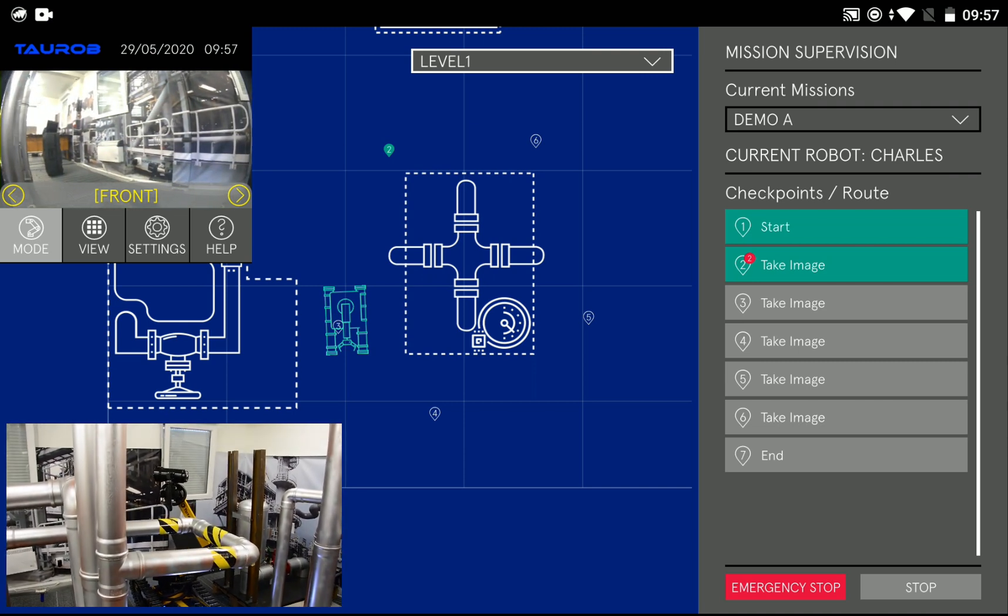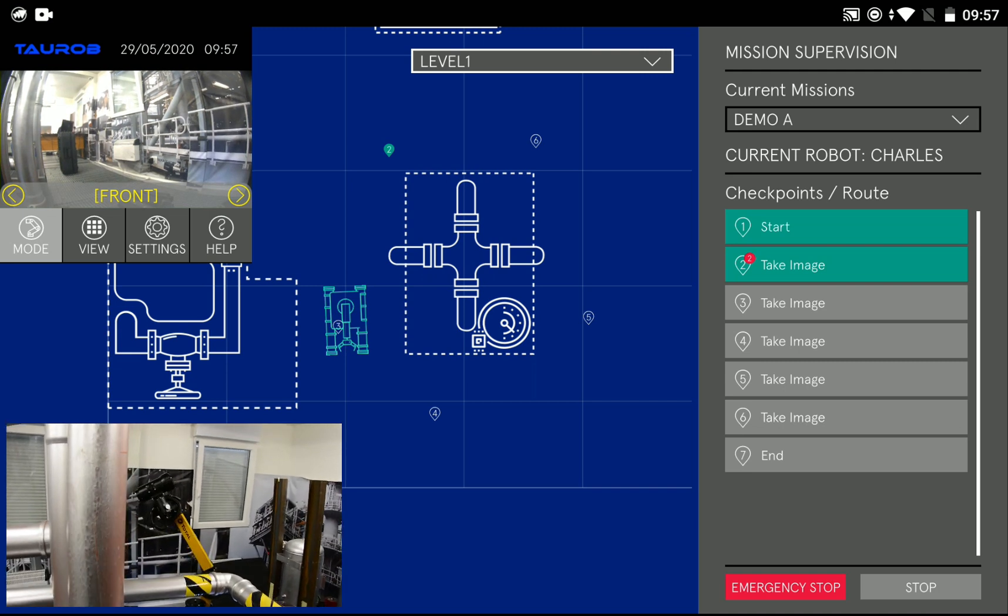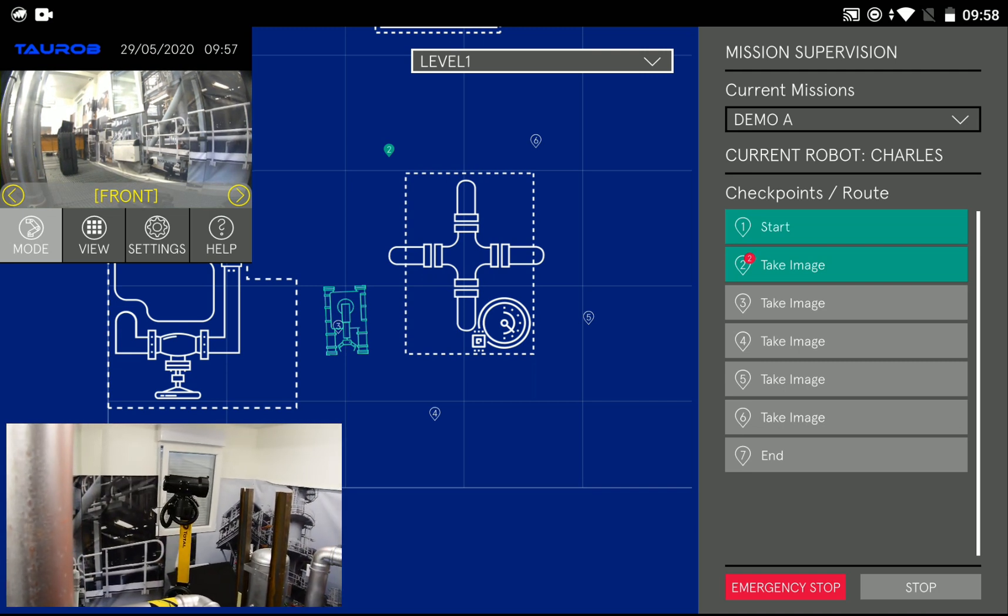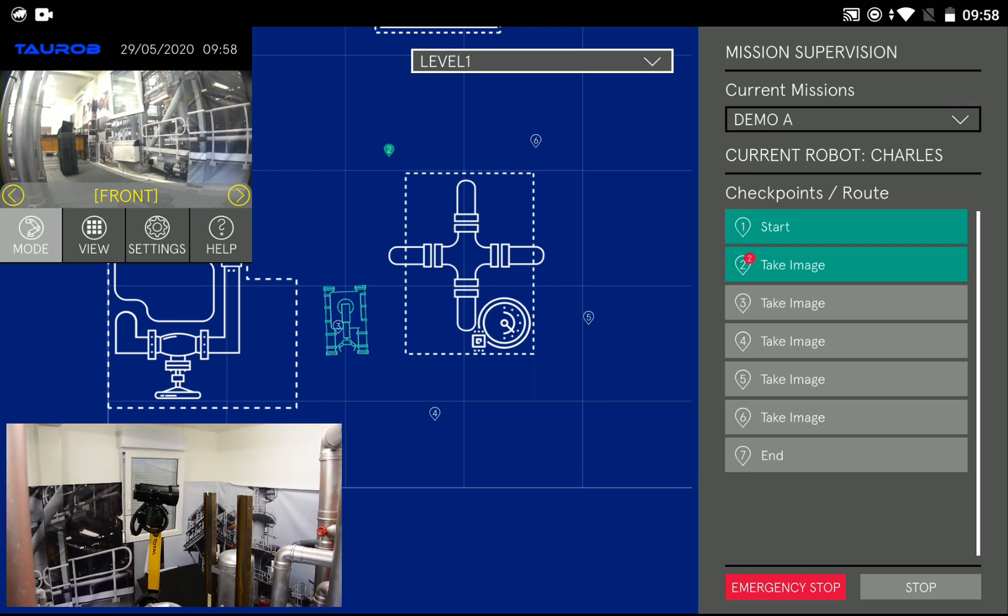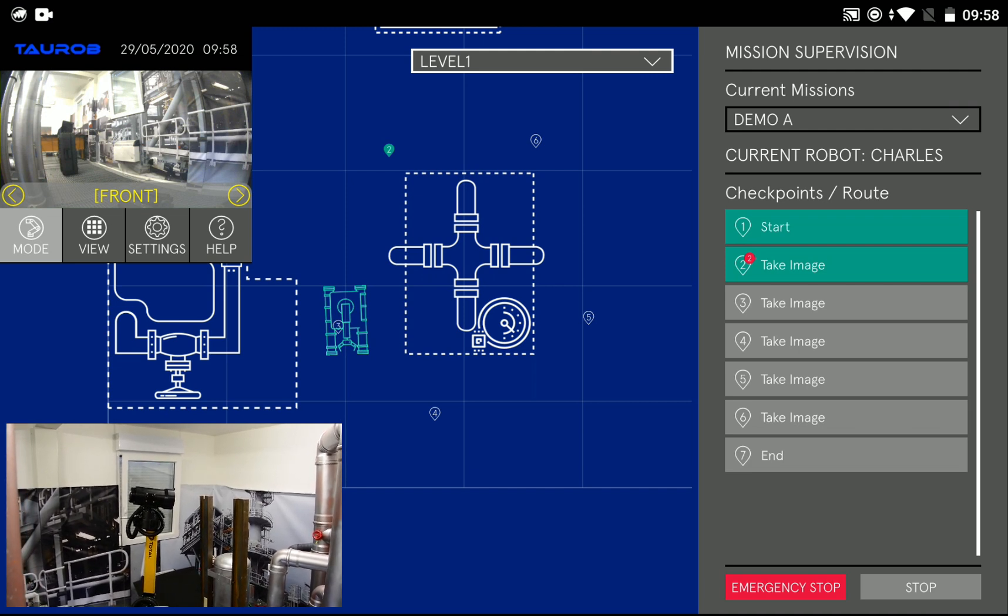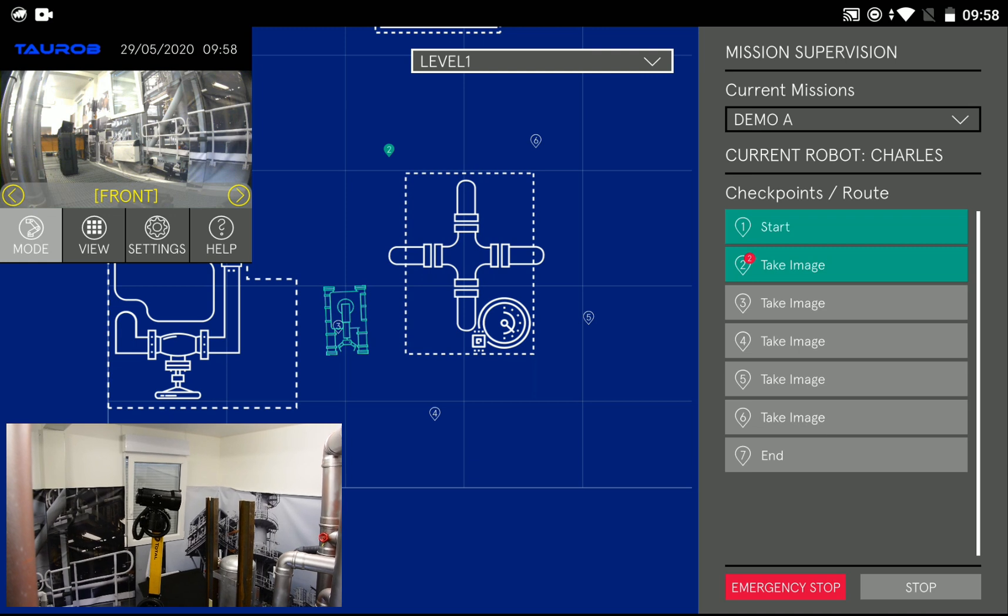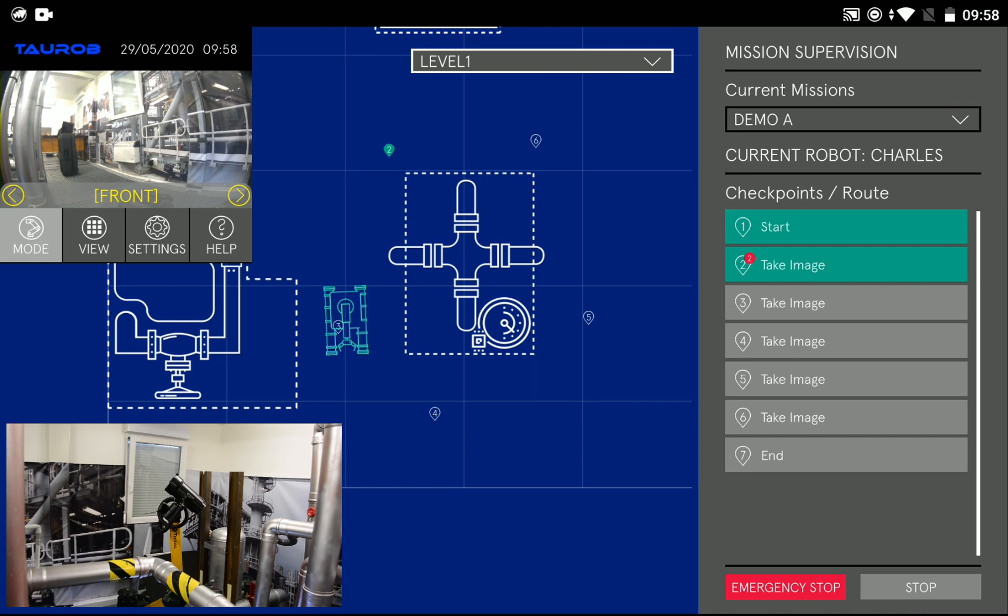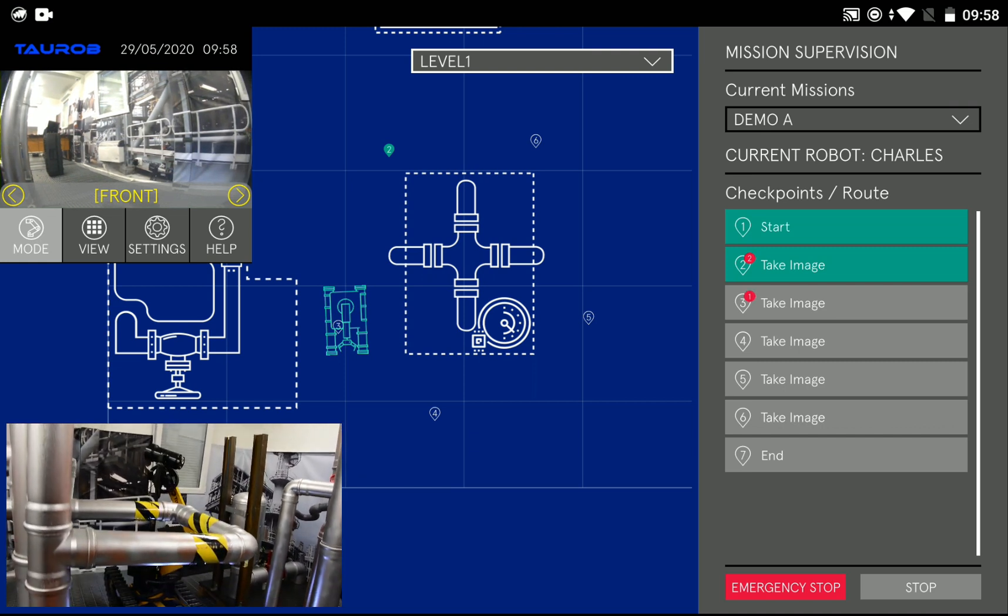In the arm we have the possibility to include a gas finding thermal camera so you can both see gas leaks and measure temperatures very accurately. It's also possible to process this data in the cloud. In addition we have a microphone so we can capture audio and analyze noise, for example determine if a pump is running normally or if a bearing is broken.